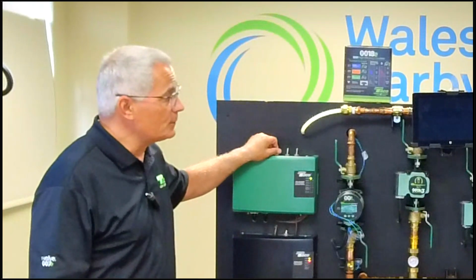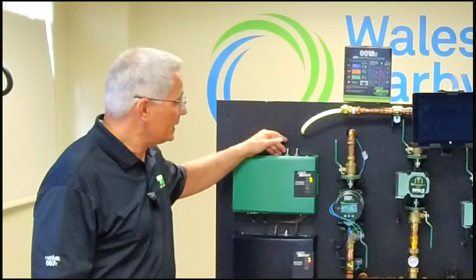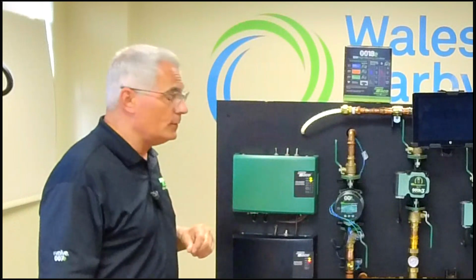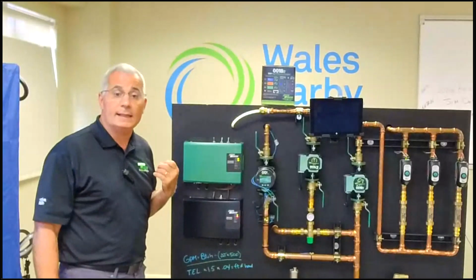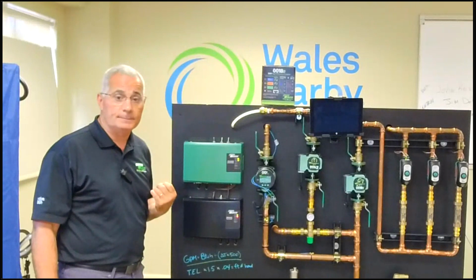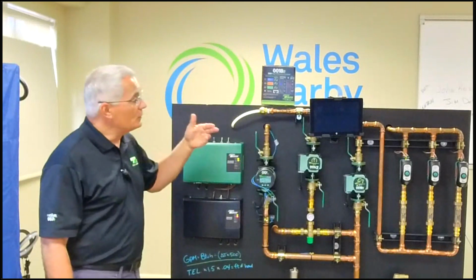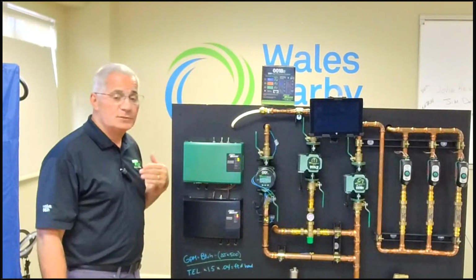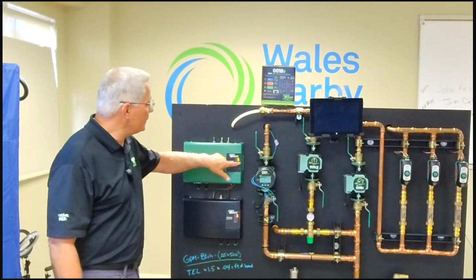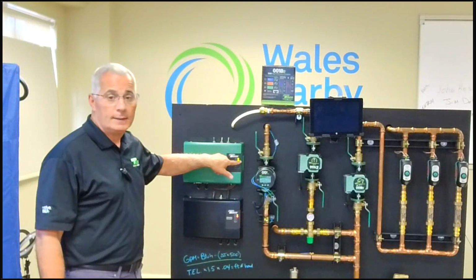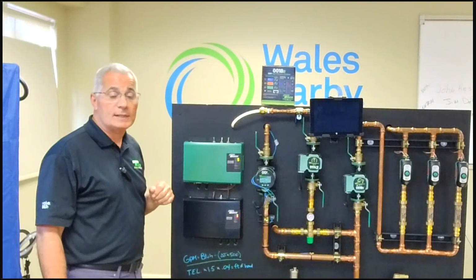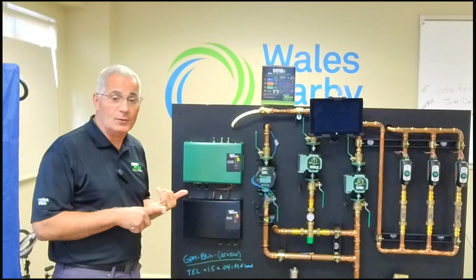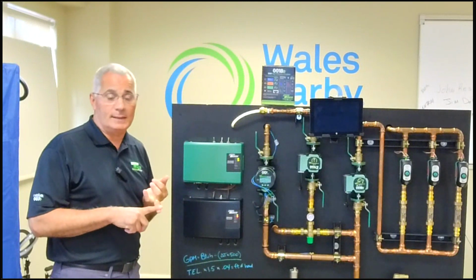I'm going to simulate some calls for heat. So I turned on one zone, and the way the panel works, when we have a call for heat, we're going to get a yellow light that lights up. When the zone valve completely opens, it's going to make its end switch, and then I will get a secondary red light that lights up per zone. So now I will know that, yes, I got a call and my zone valve opened and made the end switch.